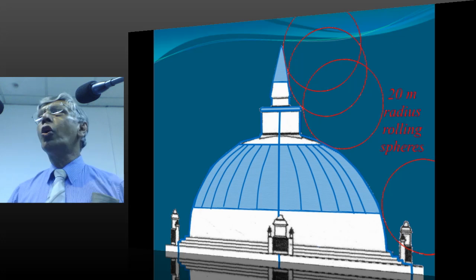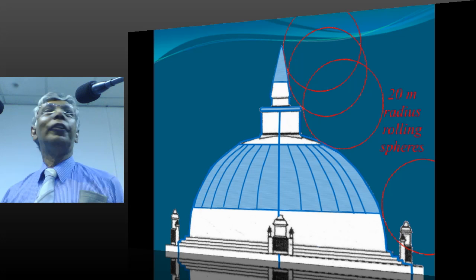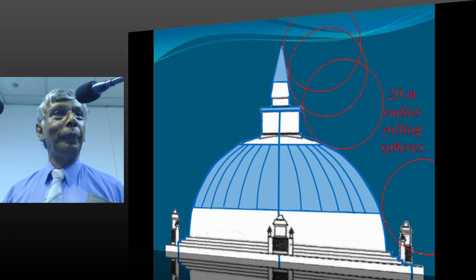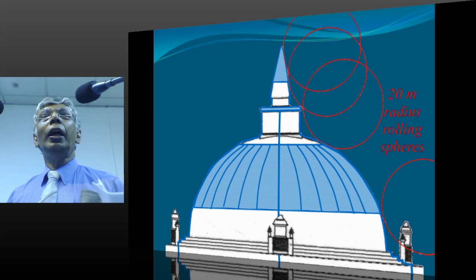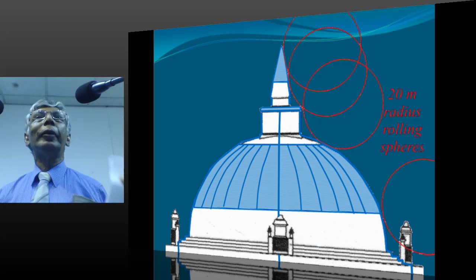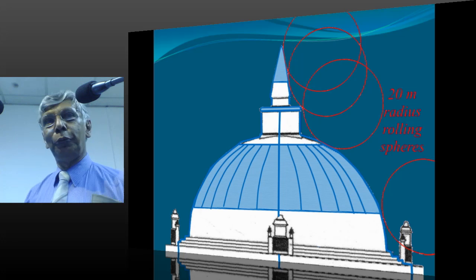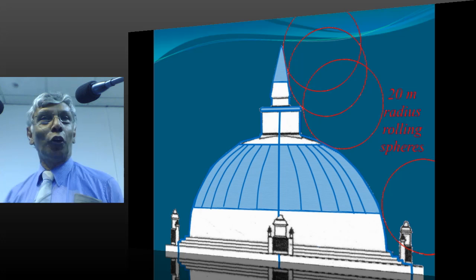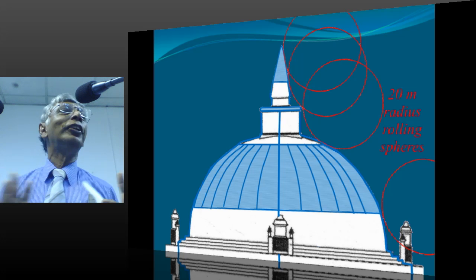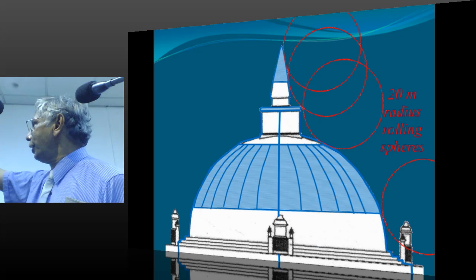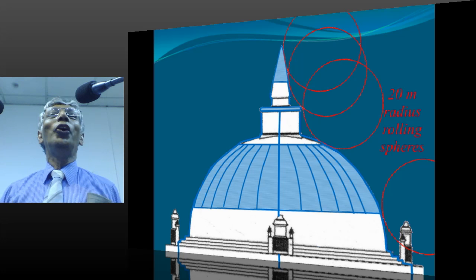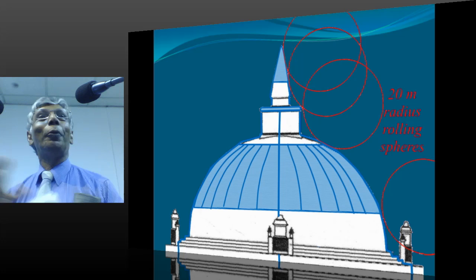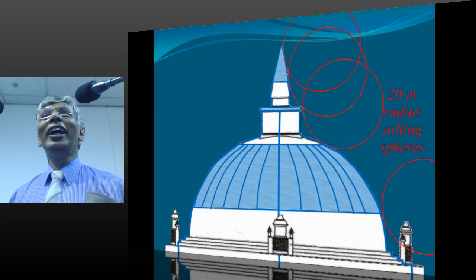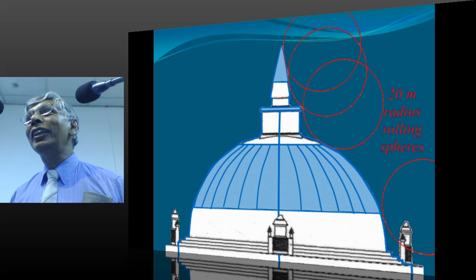If you go according to modern methods, since the stupas are more than 100 meters tall, you should use not the conical method of protection, but the rolling sphere method. If I use the rolling sphere method, without considering anything else, everything that is shown blue should be protected. So you will have copper all around, and obviously it's a waste of money.